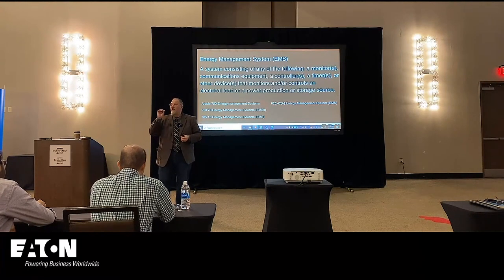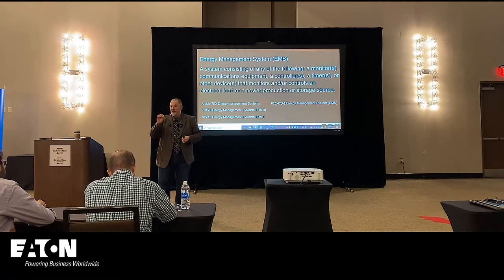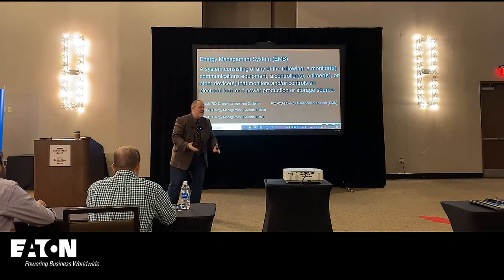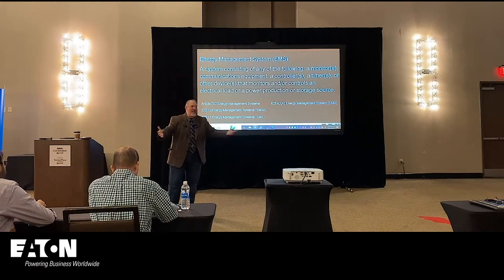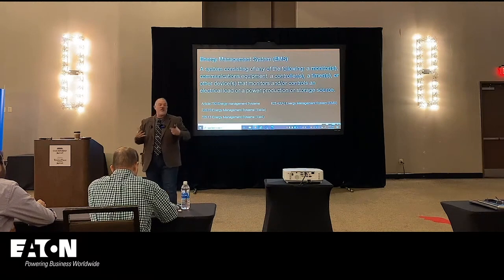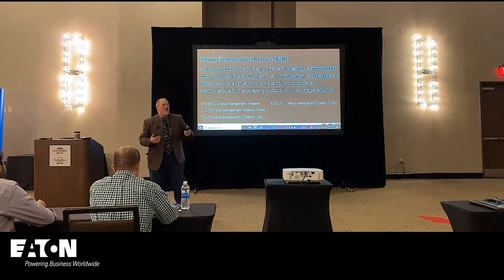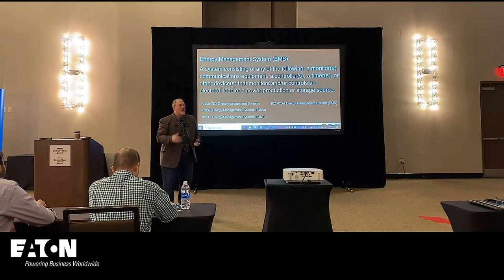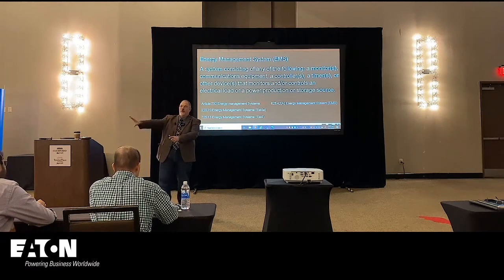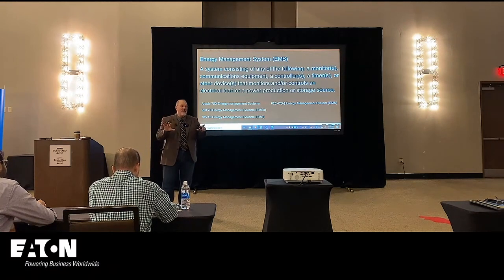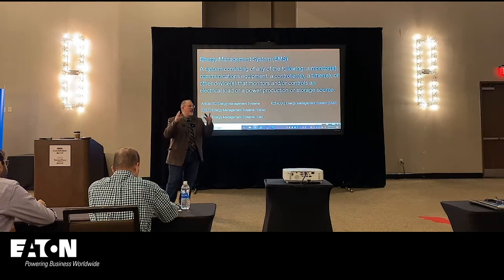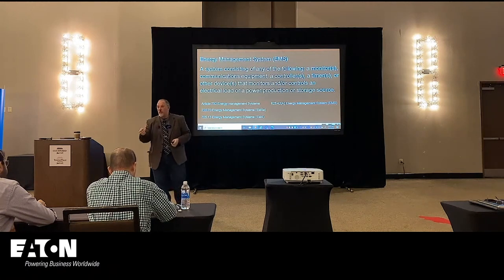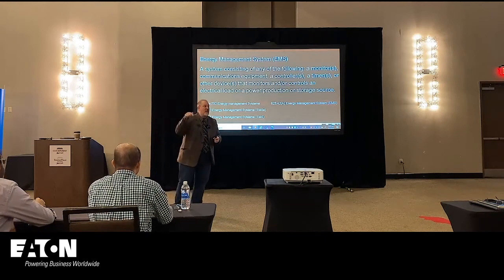Now that's a little scary because a lot of these energy management systems, if you have to do any interaction with them, what happens? You install it, and you get a pay raise and a promotion because you saved the company so much money, and then they give you a promotion and you move to another facility and the new person comes in and says, I don't know anything about it, just turn it off, right? They don't want that. They want to make sure that this is a safety-related piece of equipment now, because now I'm sizing my power distribution system based upon that set point.